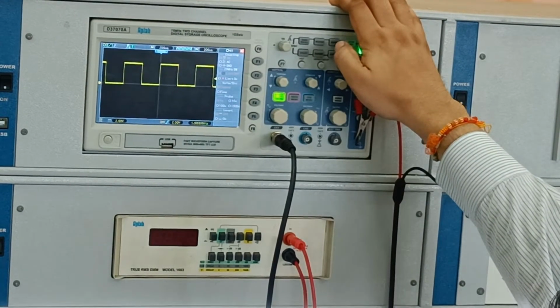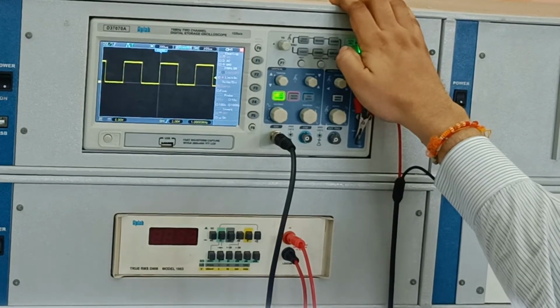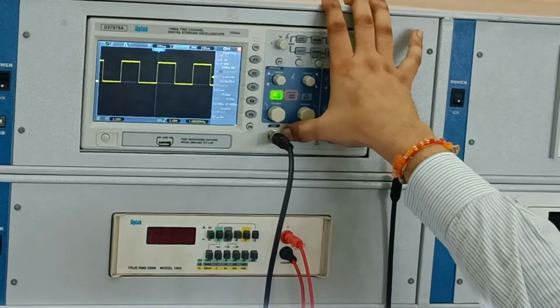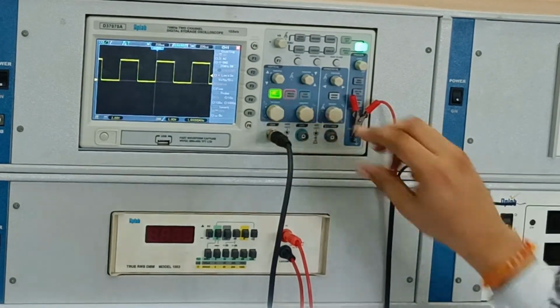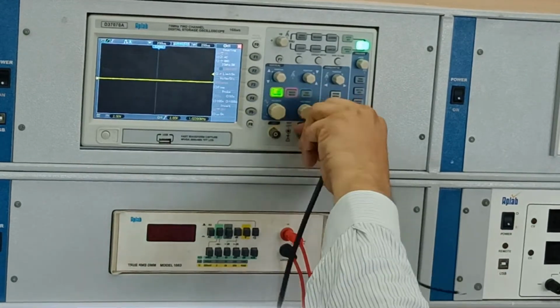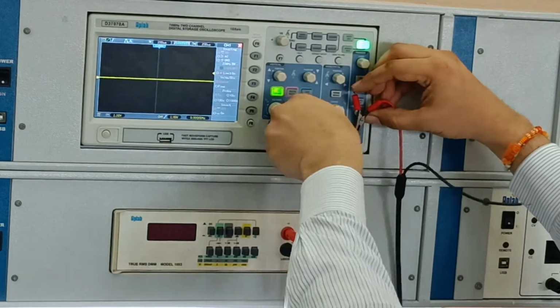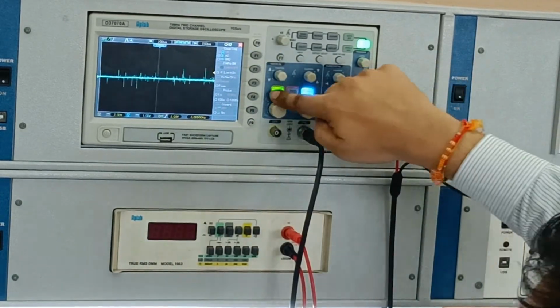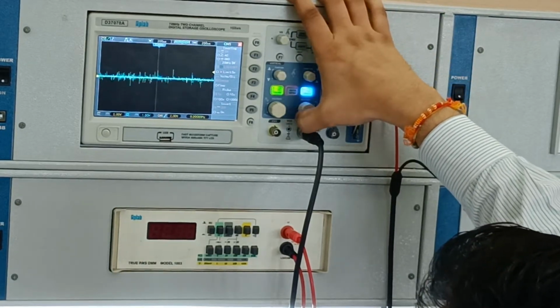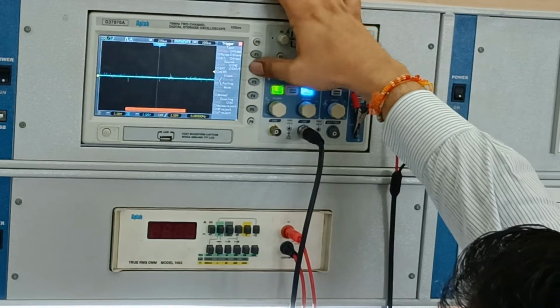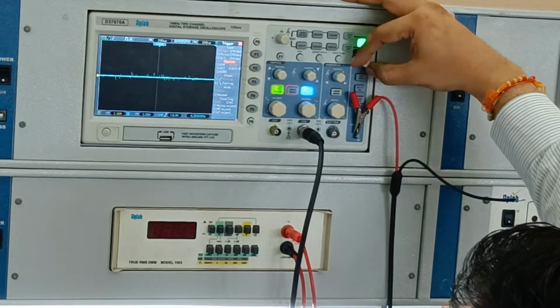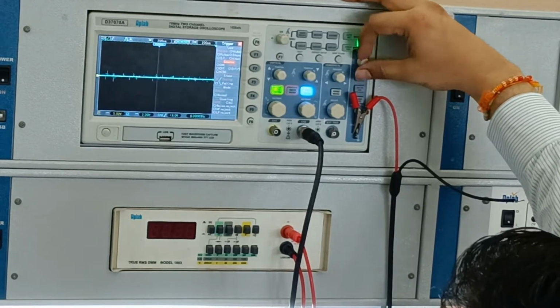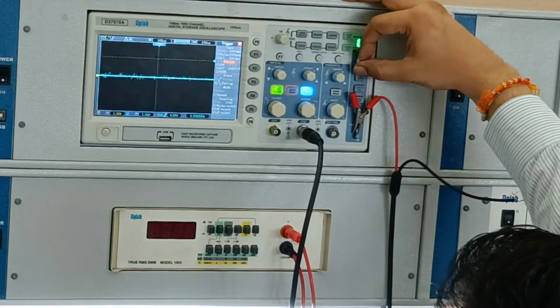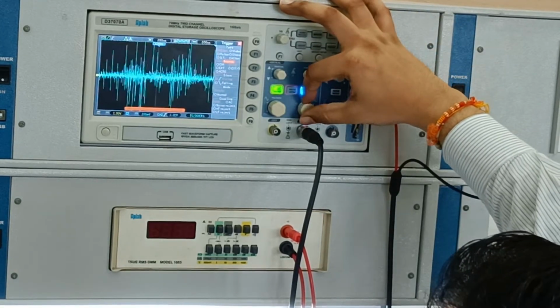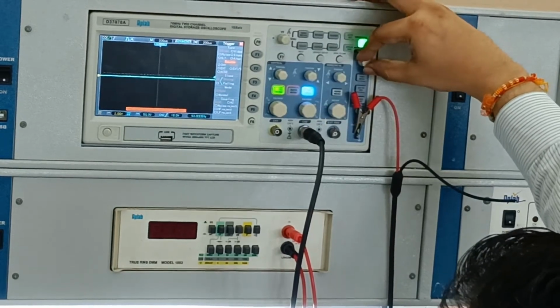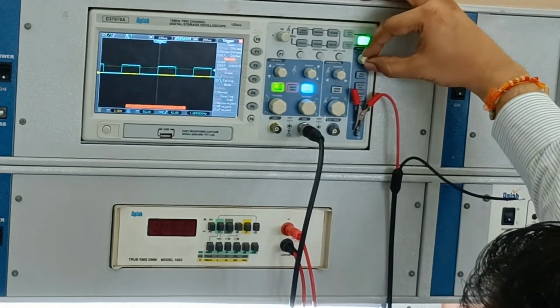If you are measuring in millivolts, try something, change the probe, or if every probe is giving like this, maybe there is some problem at the input of the oscilloscope. Try the other channel. Let us try that. Of course, then you will have to activate channel number 2, deactivate channel number 1 because it is not needed. Go to the triggering menu and change the triggering to channel number 2. Adjust the trigger level in such a way that, okay, it's upstairs. Bring it down. There is no level. Increase the volt per division or decrease the volt per division. Yeah. So the signal is there.